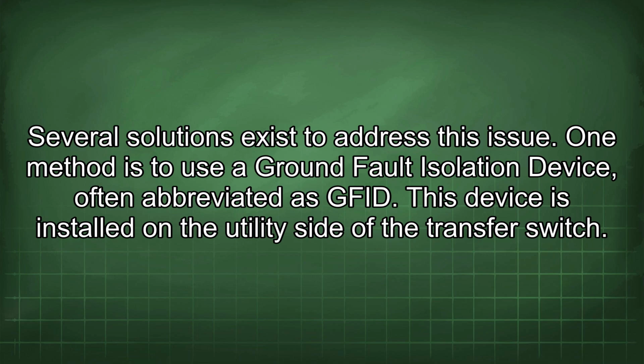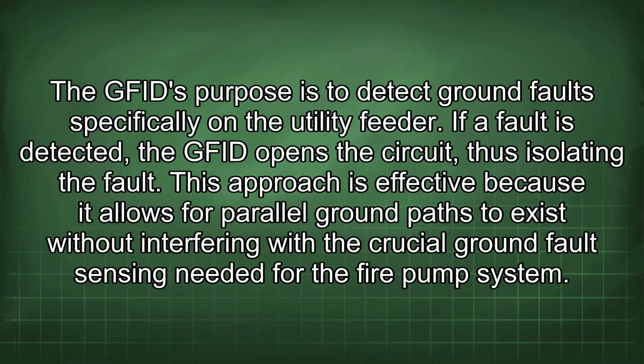One method is to use a ground fault isolation device, often abbreviated as GFID. This device is installed on the utility side of the transfer switch. The GFID's purpose is to detect ground fault specifically on the utility feeder. If a fault is detected, the GFID opens the circuit, thus isolating the fault. This approach is effective because it allows for parallel ground paths to exist without interfering with the crucial ground fault sensing needed for the fire pump system.